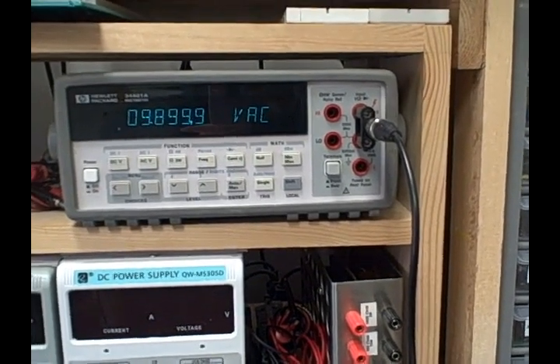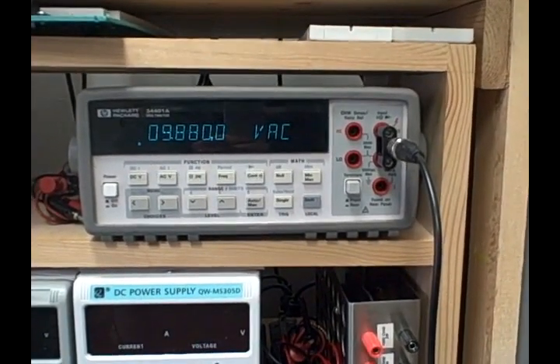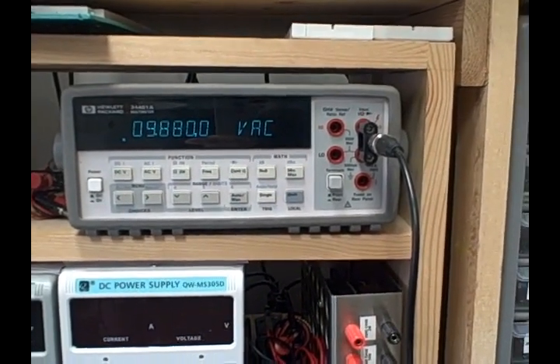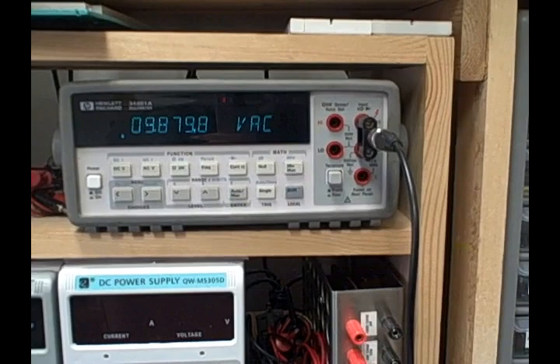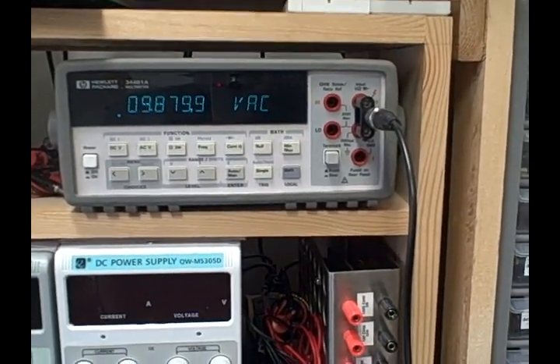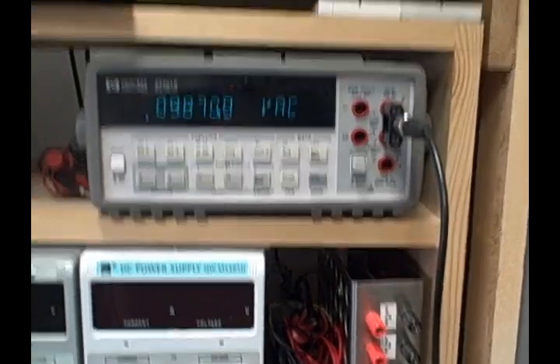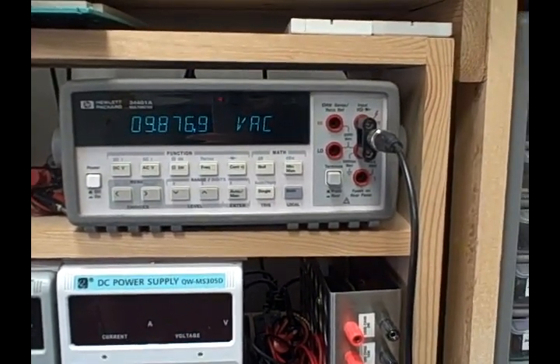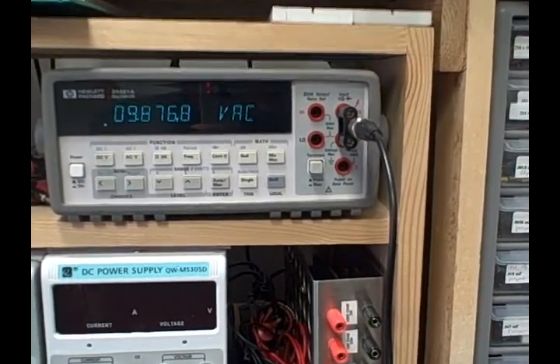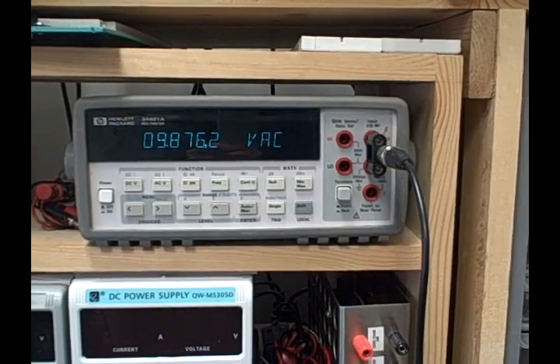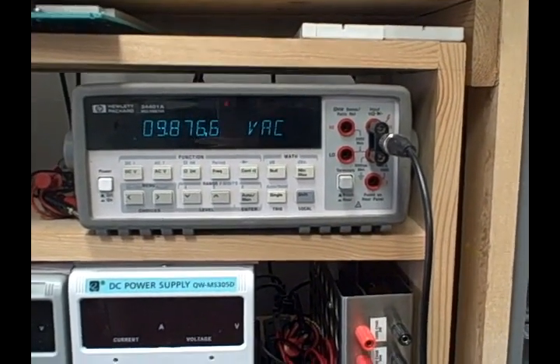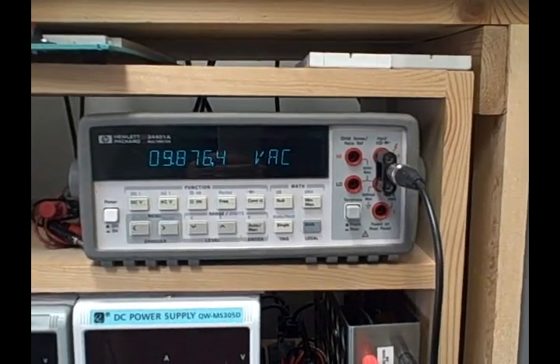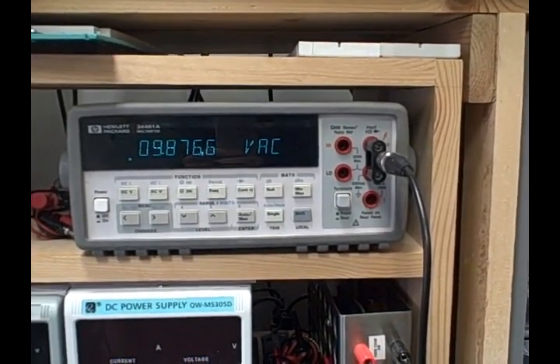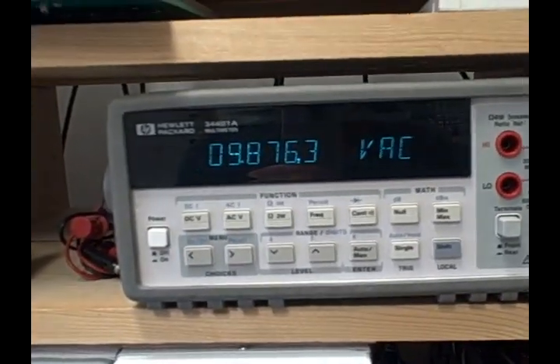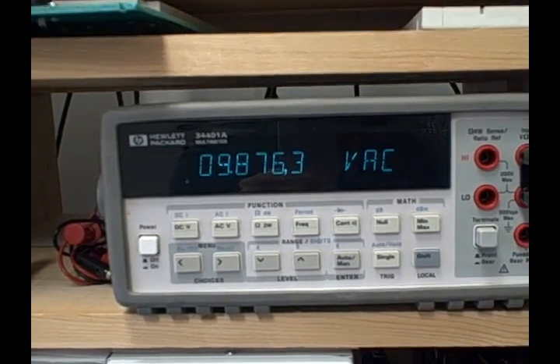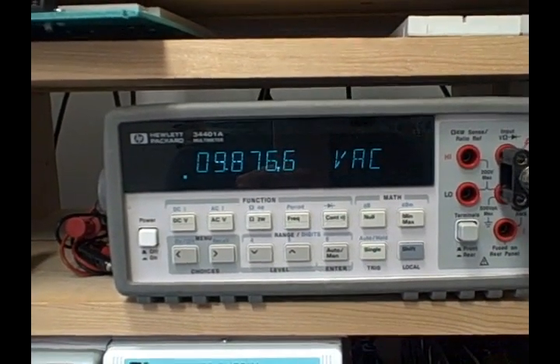If I go to the next one and say 7, now we've got 987 with two nines after, which fluctuates between 988 and 987. Let's go 6 on the 9. 9876. And then we have 9 at the end. Let's take that 9 at the end down to 5. 986, 98765 with a little fluctuation. So let's ignore the 10 millionth spot and take a look at that millivolt area there. I've got 9.876 volts, right to the millivolt, that I dialed in using this unit.